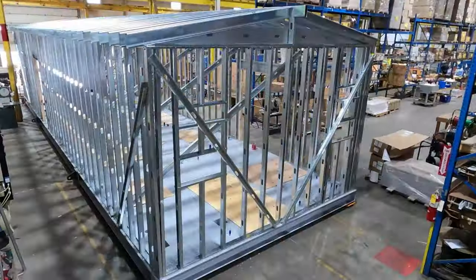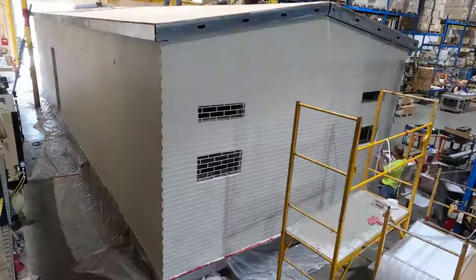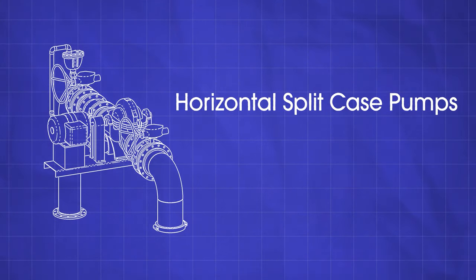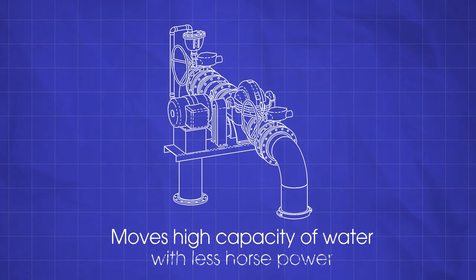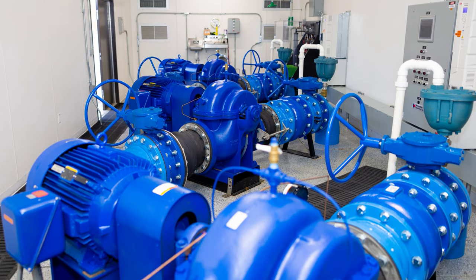The system was all built in-house within Metropolitan Industries' 100,000 square foot facility in Romeoville. Keep in mind, this is a pump station size that's bigger than 95 percent of the market that we normally build prefabricated pump stations for. We prefabricated all of the suction and discharge headers and branch pipes. Horizontal split case pumps were used inside the pump house because they are inherently designed for moving a high capacity amount of water — less horsepower required and operating at the best efficiency point on the pump curve.